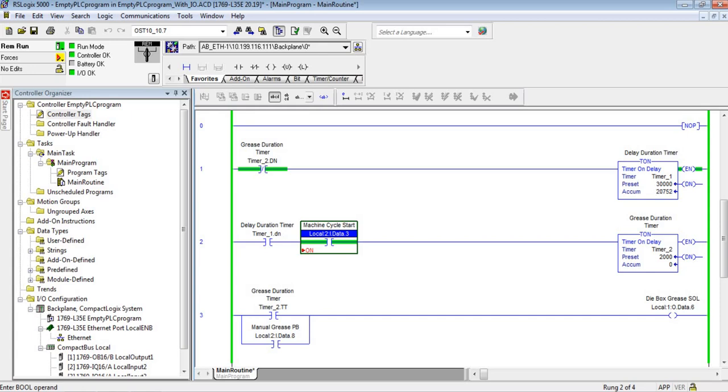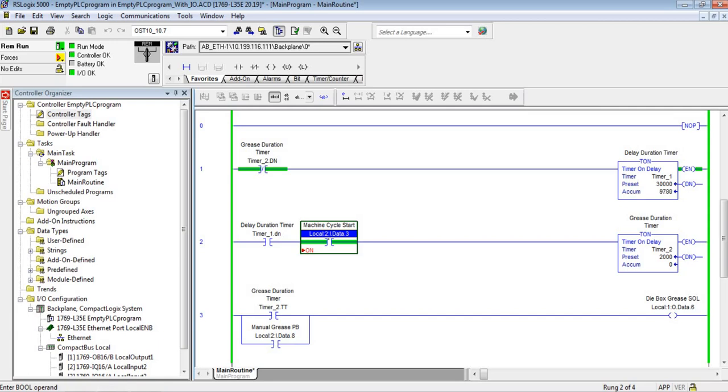This is a very common thing we have to do on machines. I also have a manual grease push button. Timer one times when timer one is done and the machine's running. So if the machine were down for the weekend and they turned it off on Friday night after the shifts were over, you don't want this thing pumping grease into a die box when the machine isn't running and isn't consuming any grease. So you have this machine cycle start contact that has to come in from an actual relay.